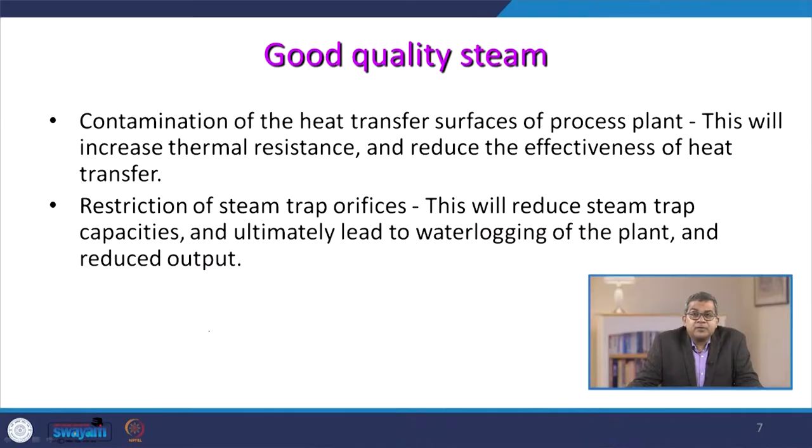Contamination of the heat transfer surface of the process plant will increase thermal resistance and reduce the effectiveness of heat transfer, which is essential for maximizing efficiency. Sometimes contaminants may restrict the steam trap orifice. If the steam trap is not working properly, it cannot distinguish between steam and water, which is extremely dangerous for boiler operation. A restriction in the steam trap orifice will reduce steam trap capacity and ultimately lead to water logging of the plant and reduce output.